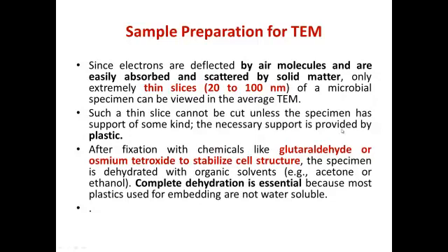For example, in the normal microtome we provide support by using paraffin blocks in which the specimens are embedded. Here, the specimens are embedded in a specific plastic structure.